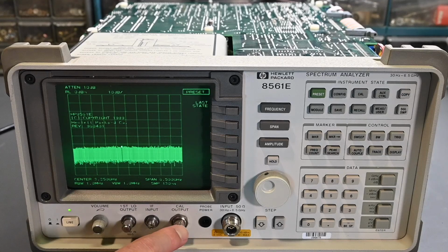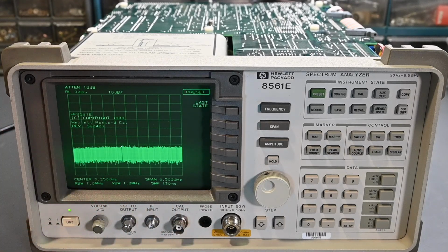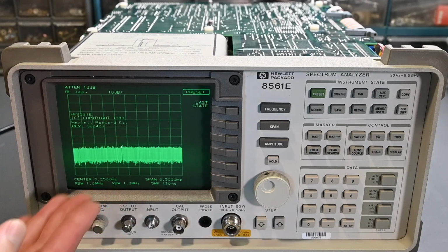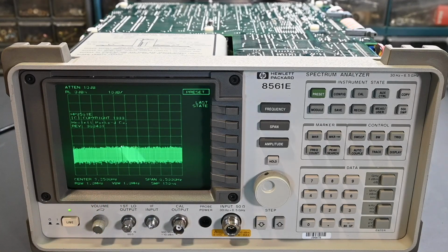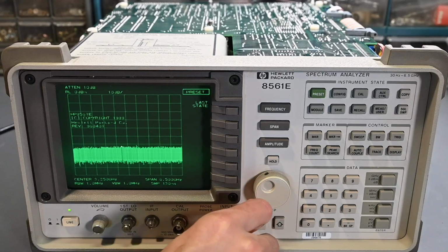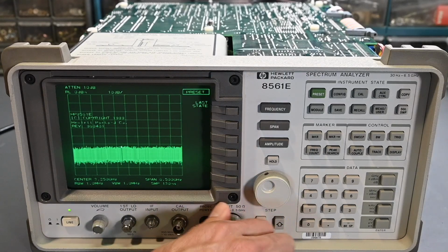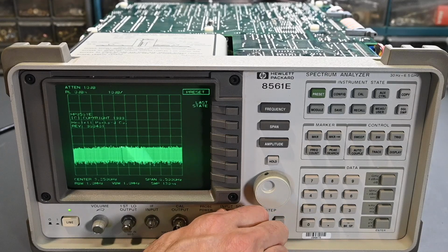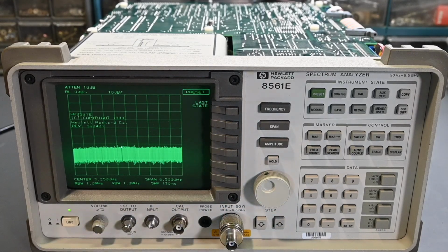As you recall in the part 1 video, the signal that came out on here, which is a 300 megahertz, minus 10 dBm signal, was displayed much too low in amplitude. Any signal that was applied to the spectrum analyzer was out of spec and too low on the amplitude value, although the higher the frequency it improved, but it never was perfect even all the way up to 6 gigahertz. So let's see if this is now displaying correctly on this reference signal, or at least very close, and then if it is, we'll connect it over to my Rohde & Schwarz SME06 RF signal generator, and we'll take some more accurate measurements.